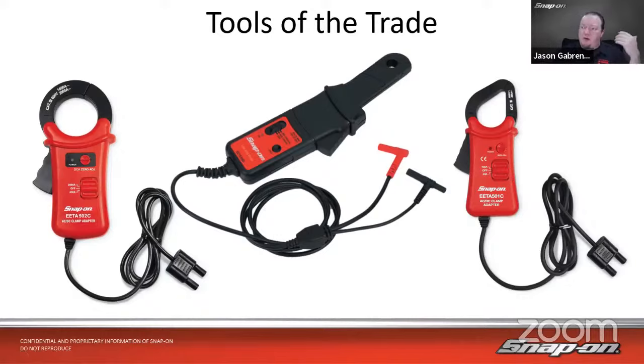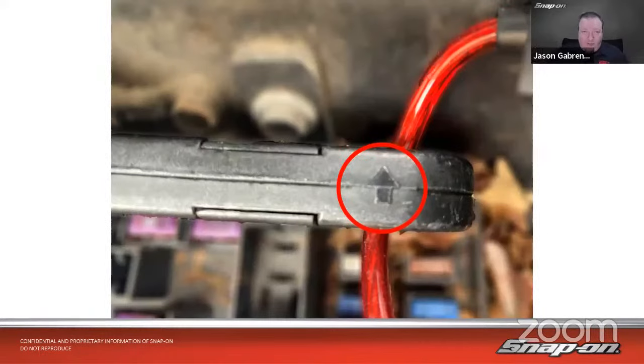You would need to go in and use the voltage setting, so they'll put out a certain amount of voltage per amp when they read the current. How an amp probe works overall is it will pick up on the magnetic field that's created, a larger magnetic field in the circuit.